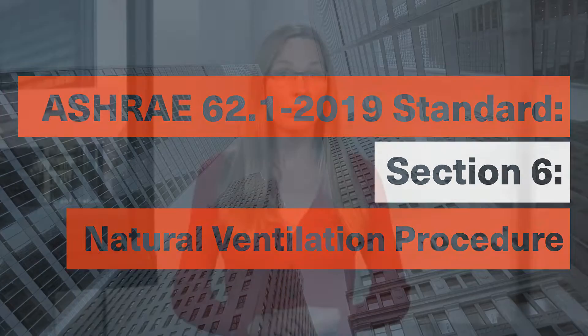The last of the three procedures allowed by the standard is the natural ventilation procedure. Natural ventilation uses wind-induced or thermally-induced pressures to draw outdoor airflow through openings in the building envelope, such as windows or louvers, rather than using powered fans.